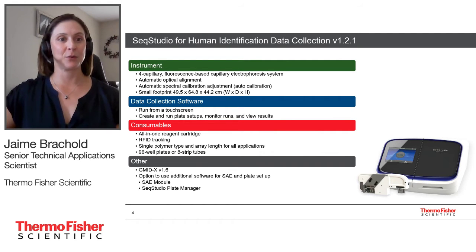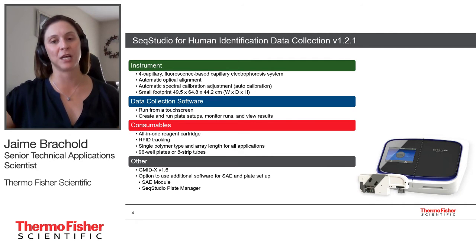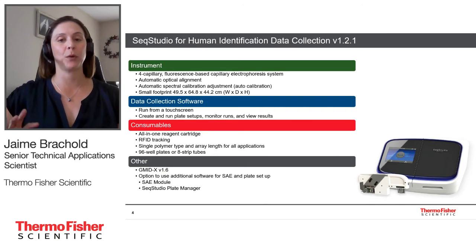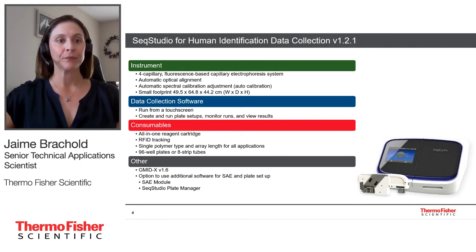You can see that this instrument is pretty small. The dimensions are there. So a nice, easy to lift, easy to move instrument to fit on a small benchtop space if that is a concern in your lab. The data collection software is run right on the instrument itself. There is a touch screen that you do everything on. You set up your plates, you can monitor your run, you view results. So there's no need to have a computer attached to this instrument at all.